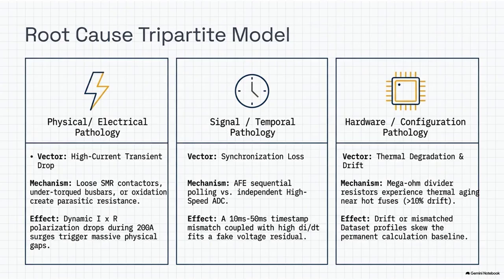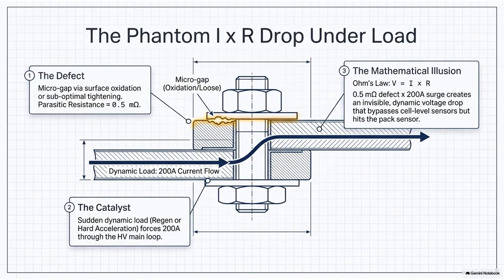That's spot on, and it's the central controller that runs the ultimate lie detector test. This is known as the dynamic cross-verification algorithm. Okay, walk us through the mechanics of that lie detector. The car is driving down the highway. What is the MCU actually computing to compare these two asymmetric systems? Every 10 to 20 milliseconds, the battery management system controller executes a continuous mathematical cross-check. It takes the absolute value of the total pack voltage reported by pathway A and subtracts the sum of the individual cell voltages reported by pathway B.